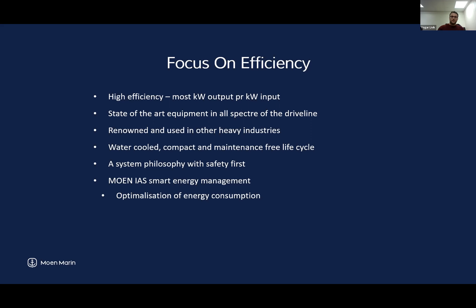In addition to the hybrid driveline, we've developed an automation system that helps the user optimize energy consumption. On a diesel mechanical boat, the motors run on idle, with the PTO supplying hydraulic power all day, even when the crane isn't running. On our system, when the crane is not running, the hydraulic unit is not running either. As soon as you touch the handles on the controller, the hydraulic unit starts. This helps the consumer preserve energy throughout the day.